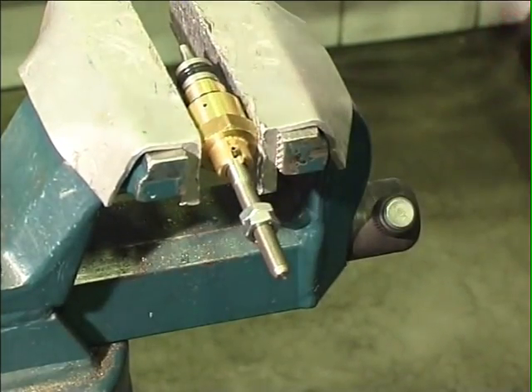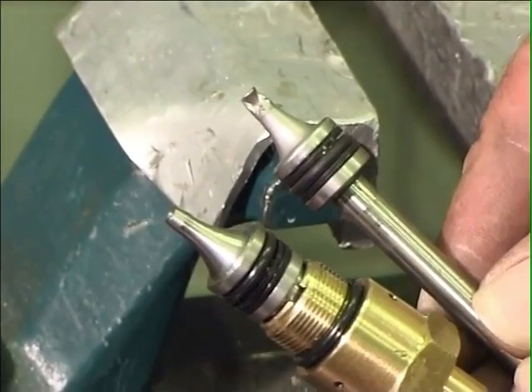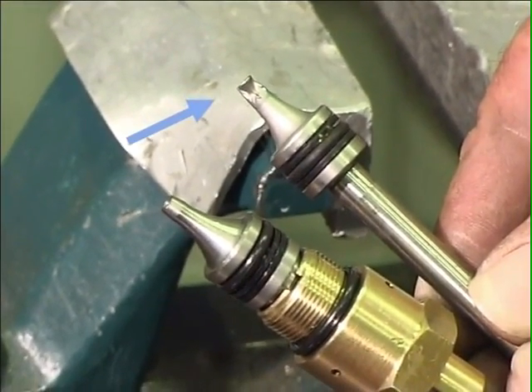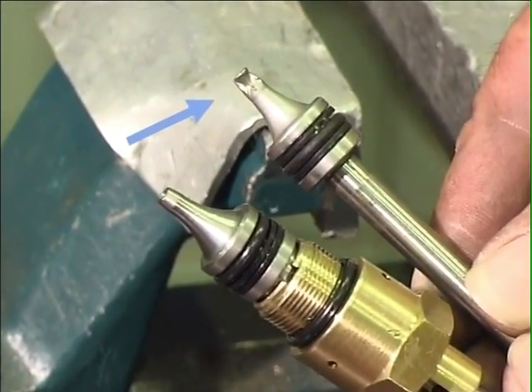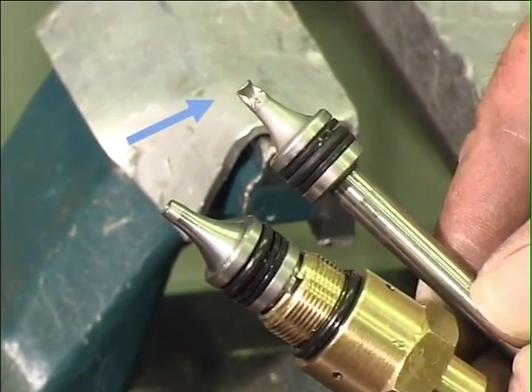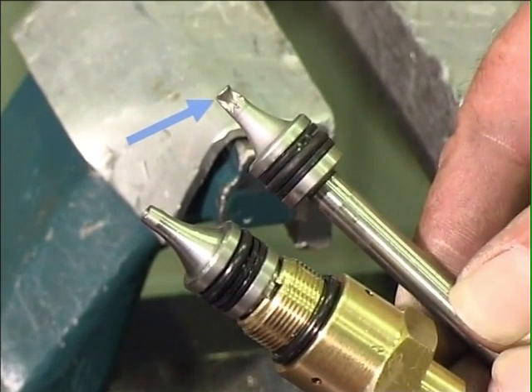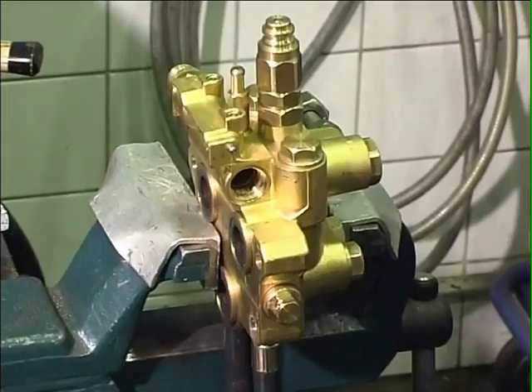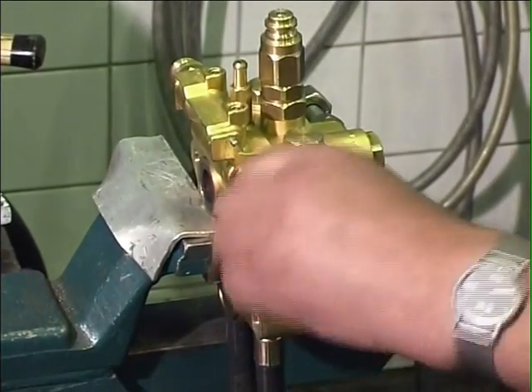Wear on the peak of the regulation piston indicates that the appliance was continuously in bypass mode due to a small nozzle or contamination to the seat and the ball. When putting the parts back together, make sure that the order of the pressure regulation is correct.